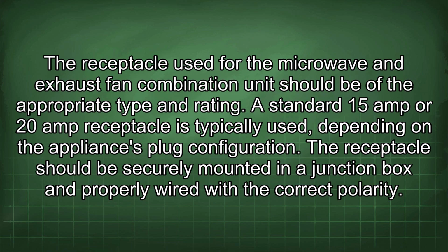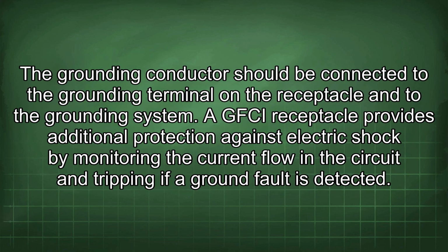The receptacle used for the microwave and exhaust fan combination unit should be of the appropriate type and rating. A standard 15 amp or 20 amp receptacle is typically used depending on the appliance's plug configuration. The receptacle should be securely mounted in a junction box and properly wired with the correct polarity. The grounding conductor should be connected to the grounding terminal on the receptacle and to the grounding system.